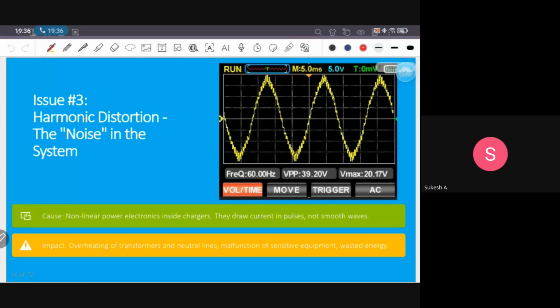So that current will flow through our distribution lines, and this distribution line will get a drop of this harmonic voltage. Harmonic current into grid impedance will give a harmonic voltage drop, and our consumer equipment will get affected with this harmonic voltage drop.